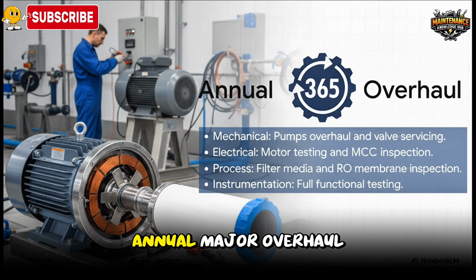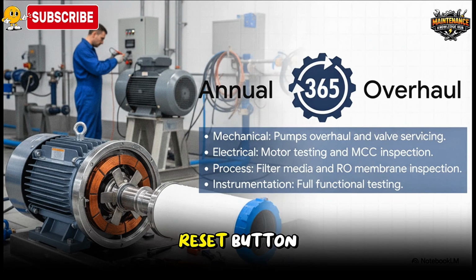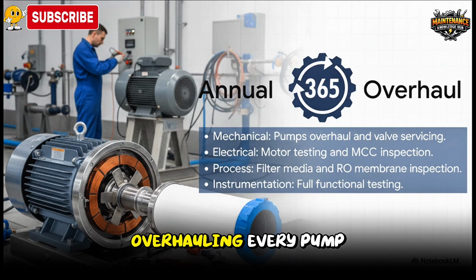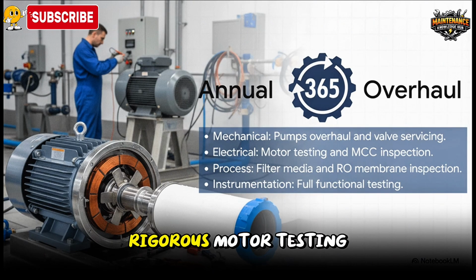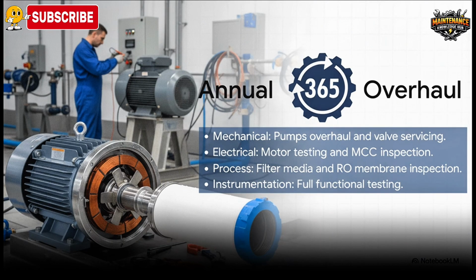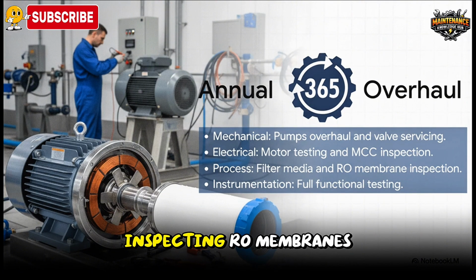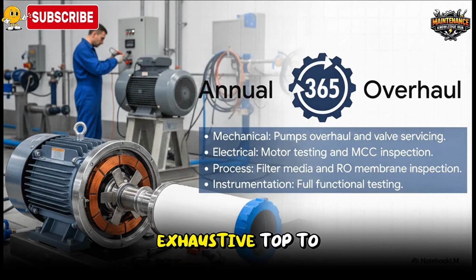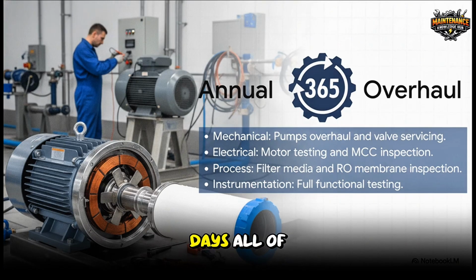And then, the annual major overhaul. Think of this as the ultimate reset button for your entire facility. We are talking overhauling every pump, replacing bearings, fully servicing valves. On the electrical side, rigorous motor testing and cable inspections. Your process equipment gets evaluated, testing resin quality, inspecting RO membranes. It is an exhaustive top-to-bottom physical to make sure the plant runs smoothly for another 365 days.